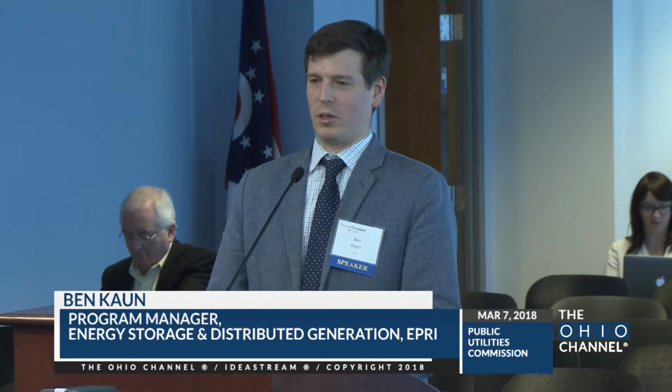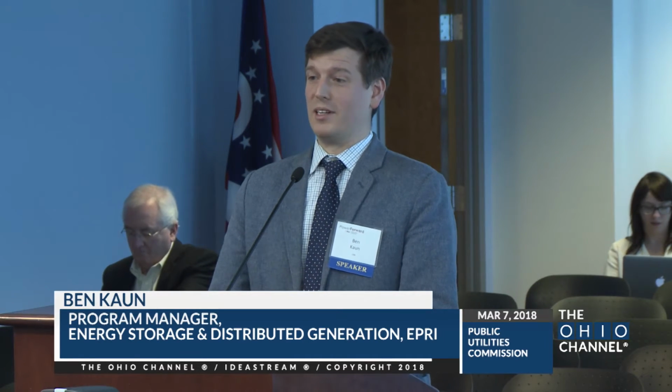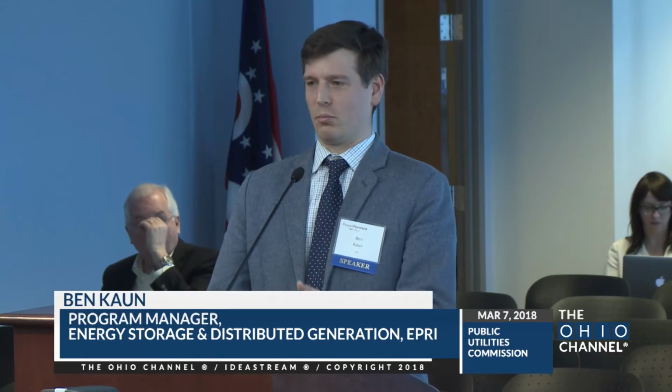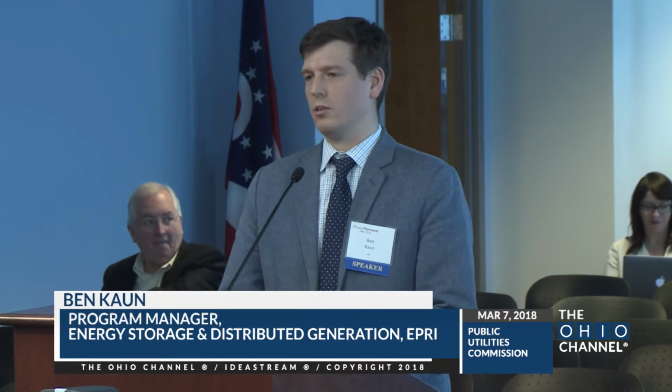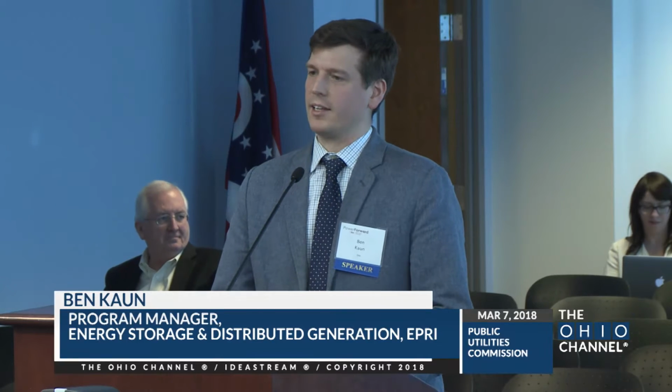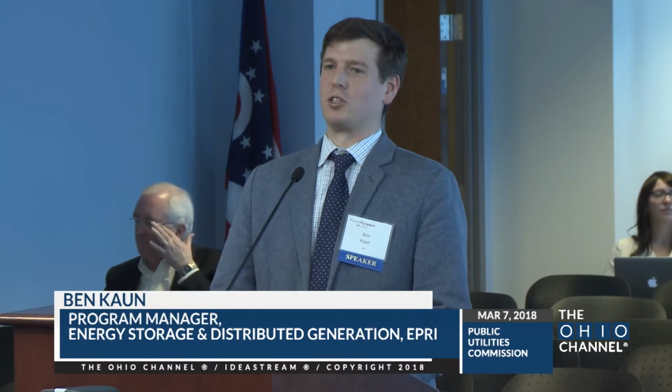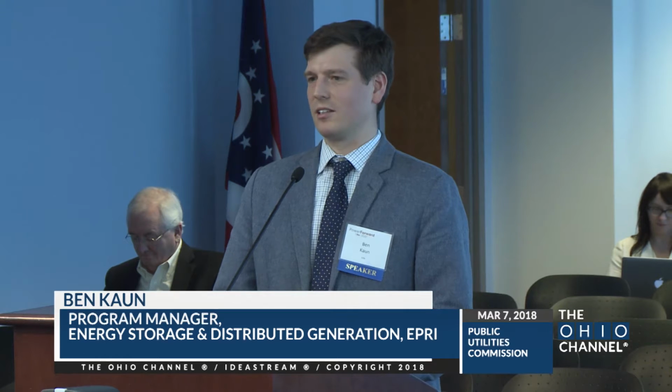And that's all the components in the whole energy storage project, which can be rather complicated. And there's even a number of mundane issues that need to be looked at. I've got a picture here on the bottom of a rodent that chews through a line and takes down a storage system. These kinds of things you don't necessarily get to experience until you've had some experience operating them out in the field and maintaining the systems.